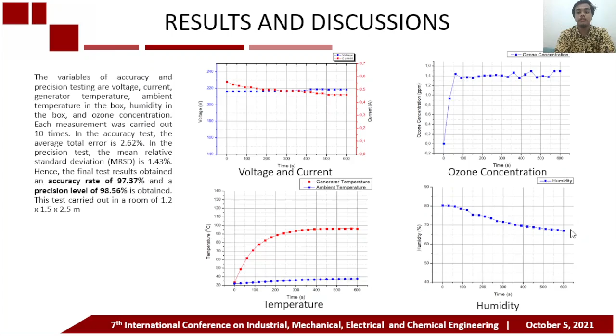And for the temperature, the red line is the generator temperature, where the maximum generator temperature was 96 degrees Celsius, and the maximum ambient temperature was 39 degrees Celsius. And the humidity dropped from 81% to 68%.